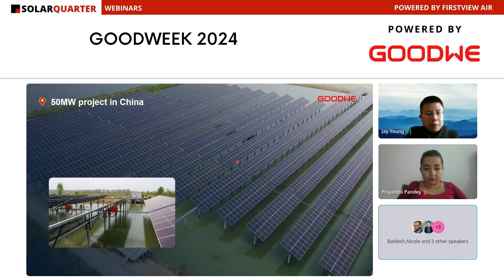So the last part is our case references. This is our project in China. It's 50 megawatts. We are using the UT inverter. You can see the inverter is above the lake, about 2.5 meters above the lake. So the humidity is very high. And for the inverter itself, we have IP66 and C5 corrosion level protection, so we can ensure our inverter can be very reliable in this environment. And also, this environment is not so friendly for the modules. It is very easy for the modules to get the PID effect, and our inverter has a PID solution to prevent the PID effect.